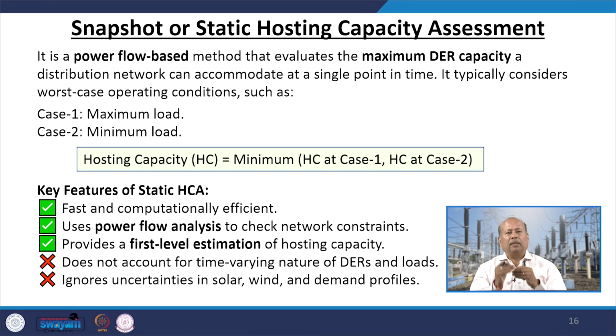So, we will determine the hosting capacity during maximum loading condition, we will determine the hosting capacity during minimum loading conditions, and then we will take the minimum of both to determine the overall hosting capacity of the network. Now, what are the key features here? It is quite fast, computationally efficient, and uses power flow analysis to check network constraints and provide a first level estimation of hosting capacity.